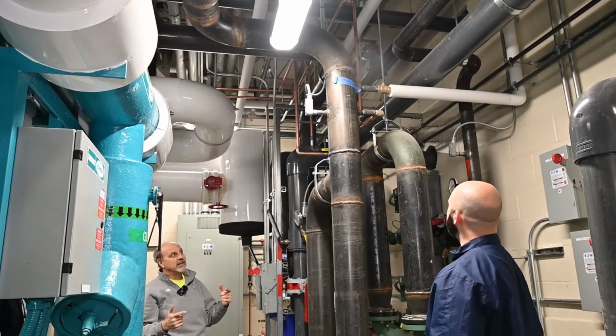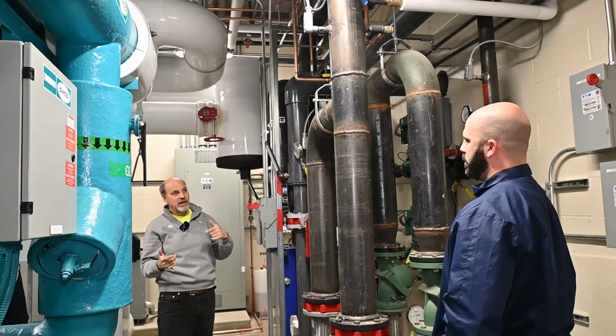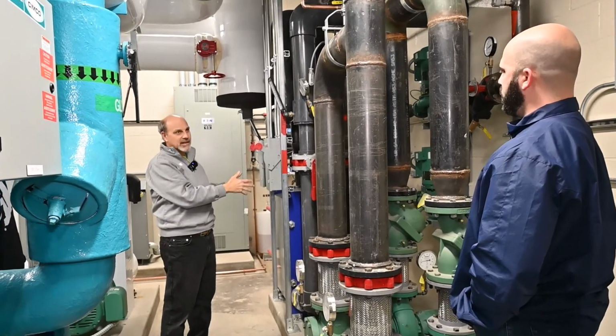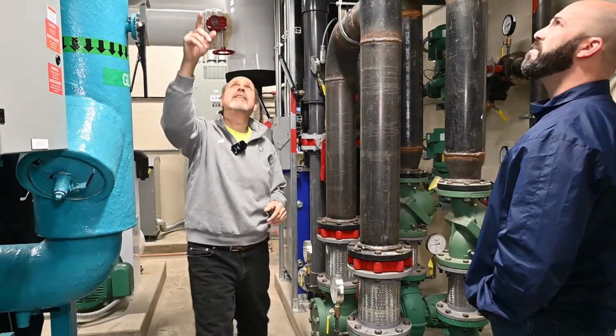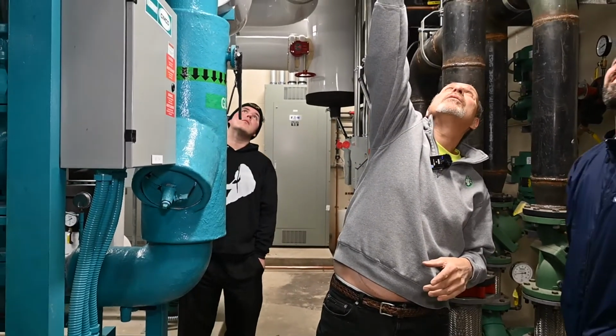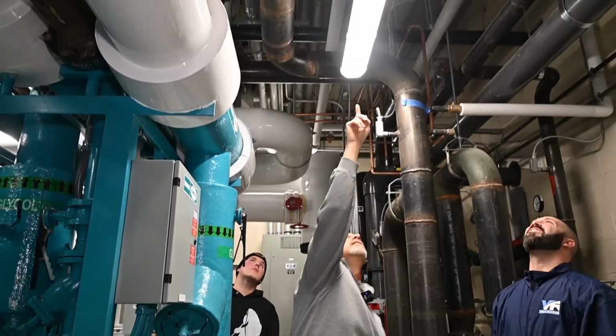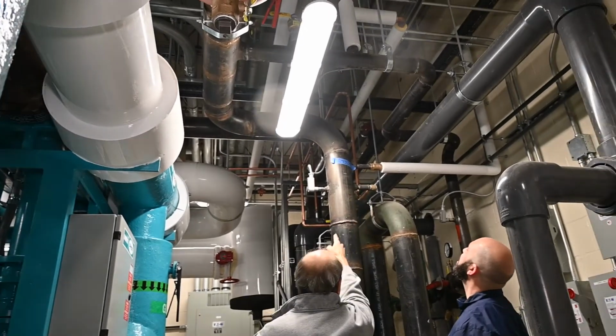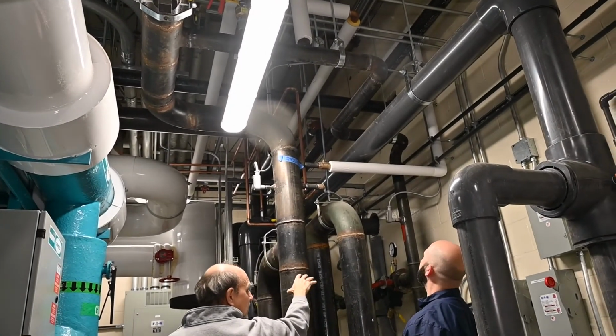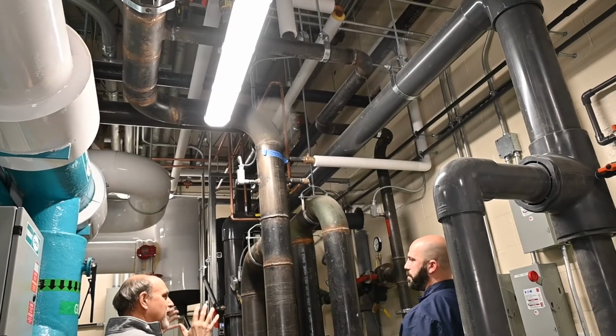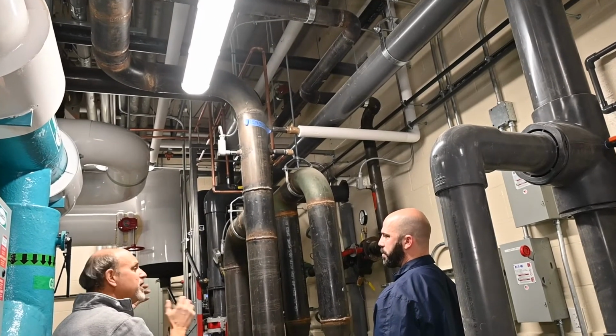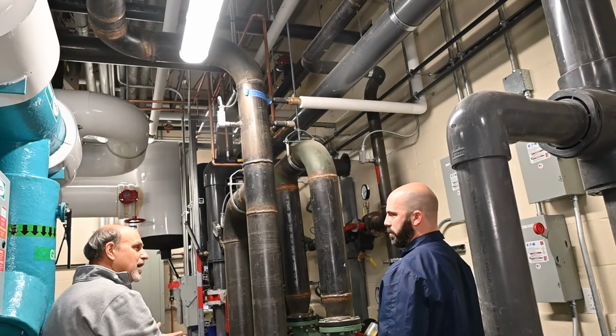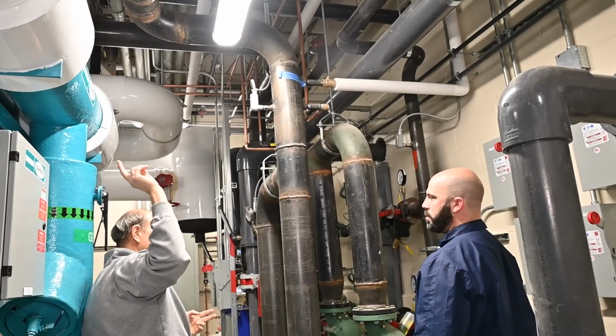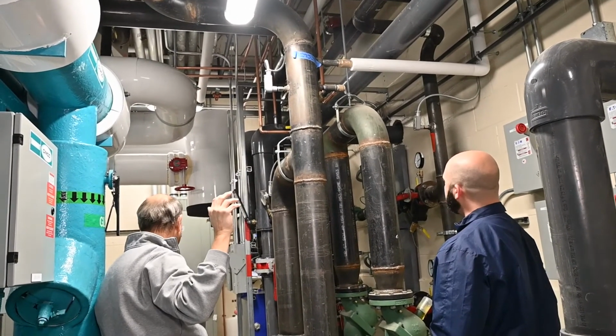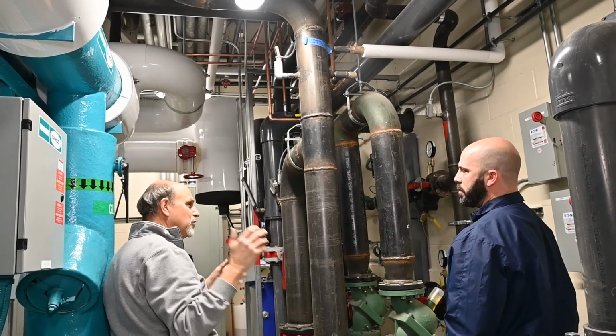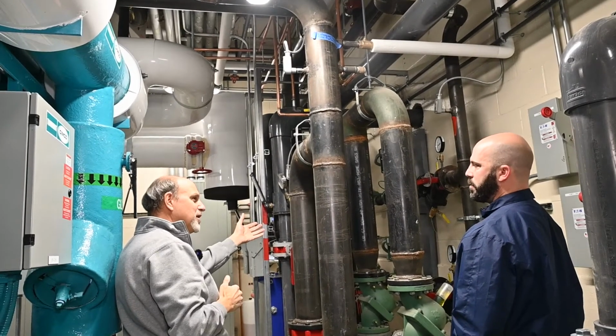And then the final thing is you're preheating your domestic water. That also comes off this glycol loop. So what we did here is, you can see that copper pipe off the top. Yep. It comes over, it ties into this copper pipe, and it goes through the wall up into your Zamboni room. And that is the entire preheat system for your Zamboni water, for your showers, what have you. So we're doing 2 things. We're pulling off that warm glycol loop to preheat your warm floor, but also we're grabbing whatever heat we can to preheat domestic water. Okay.